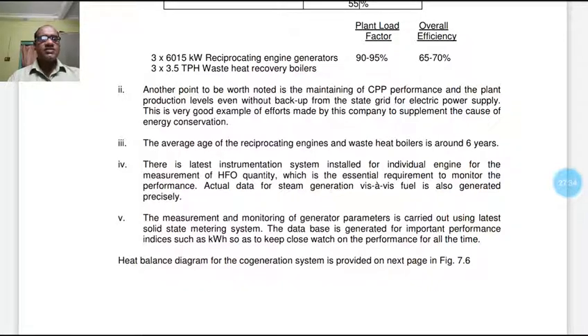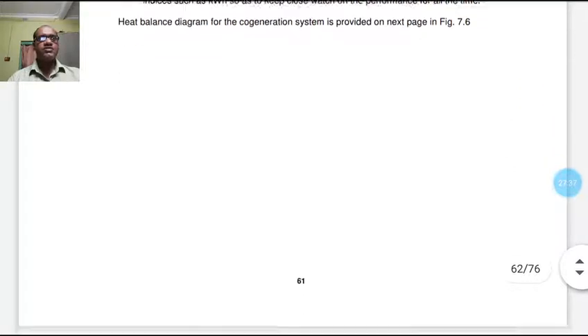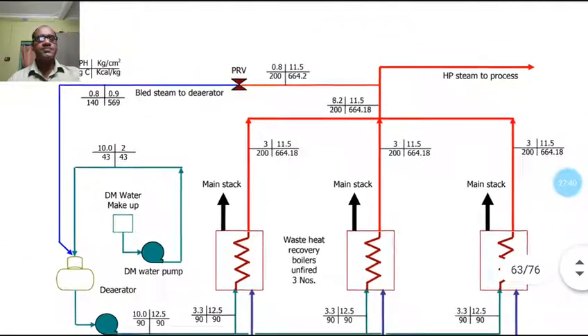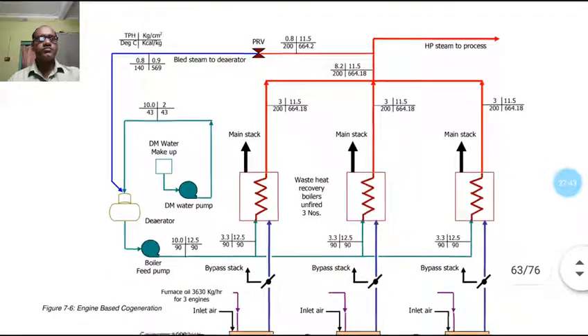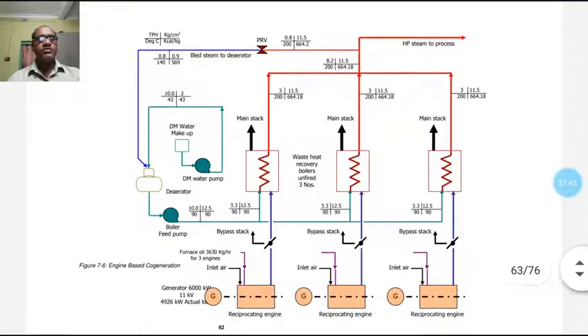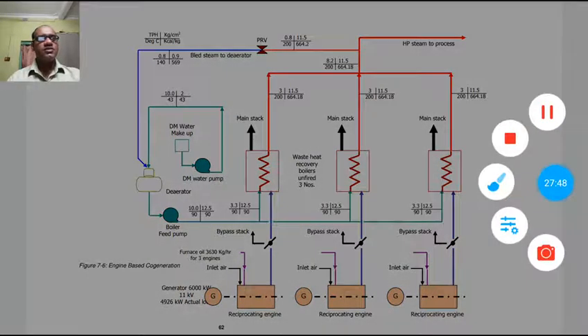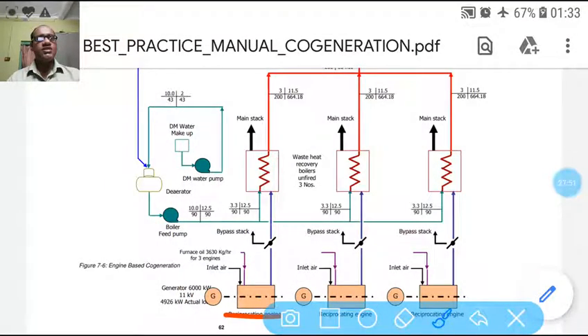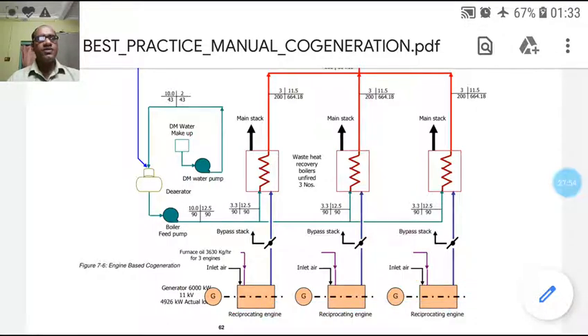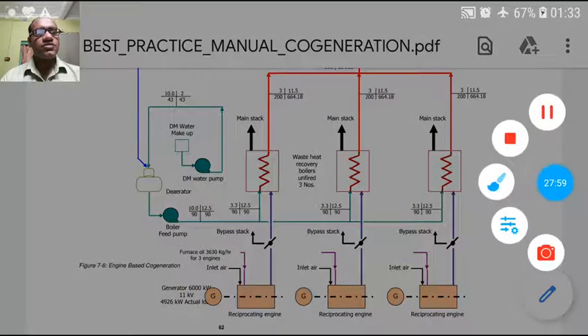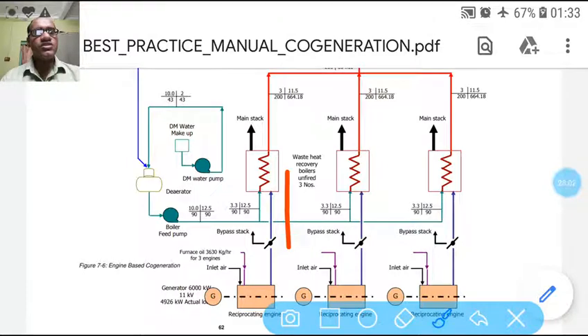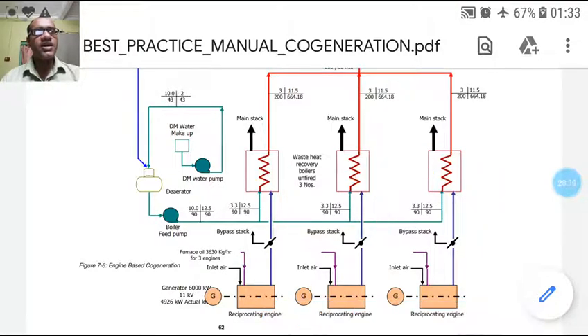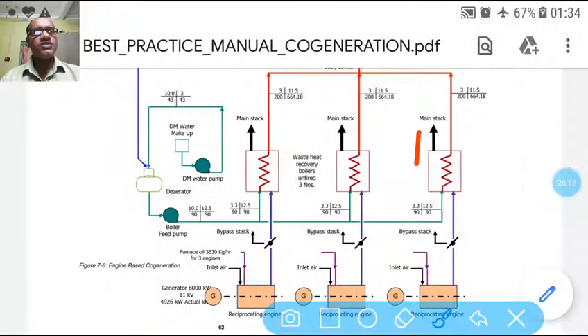Now the heat balance diagram for this cogeneration system is shown on this page. So 3 reciprocating engines, as we can see, are there. They are primarily producing power, and the exhaust from these engines is going to the waste heat recovery boiler. These are all the waste heat recovery boilers, and after that the exhaust gas is moving to the main stack.